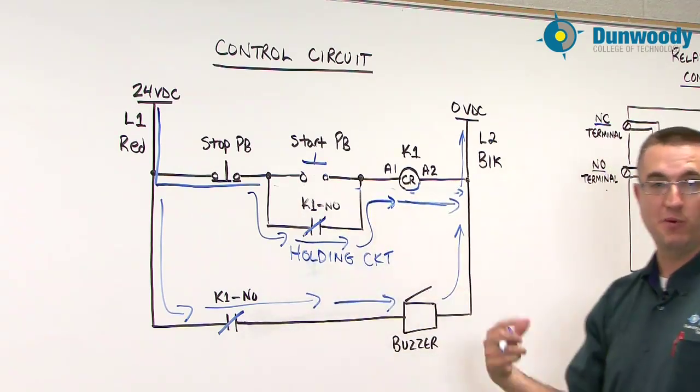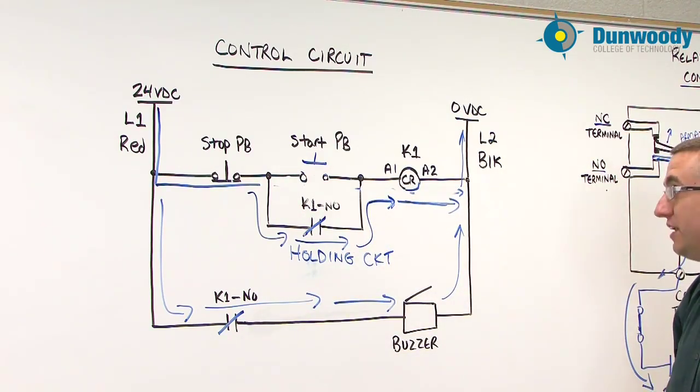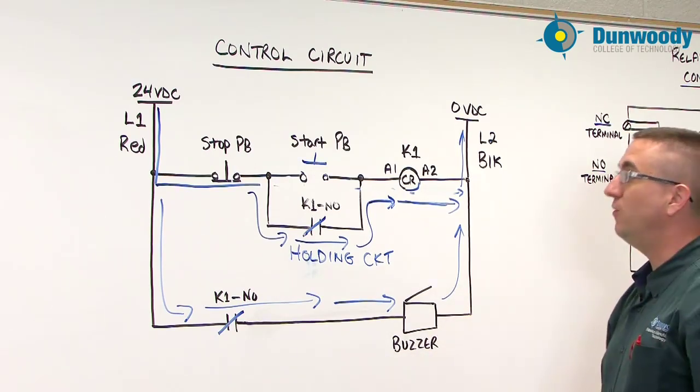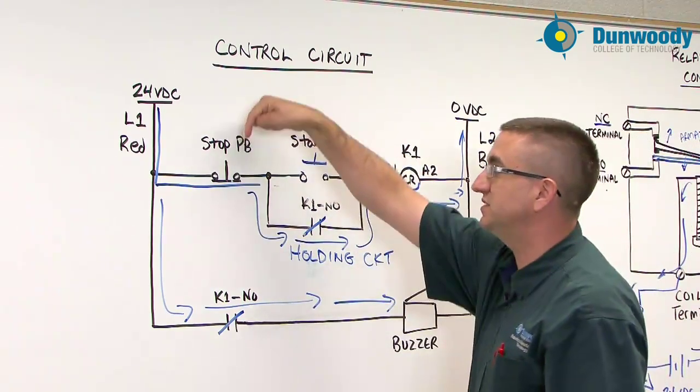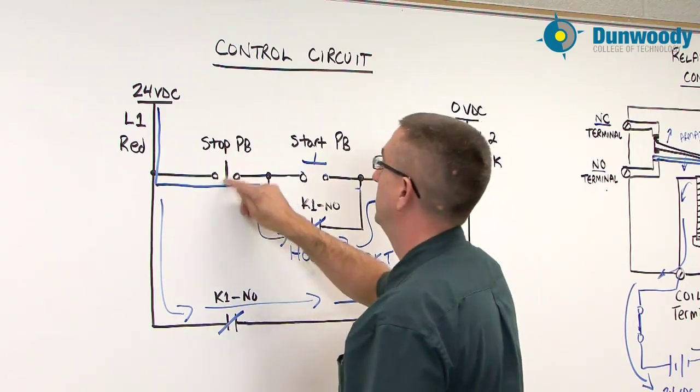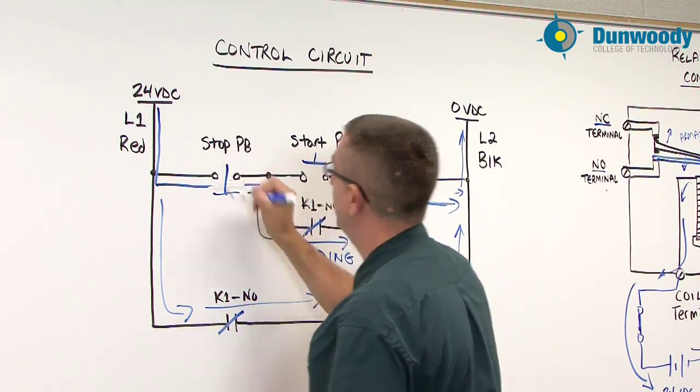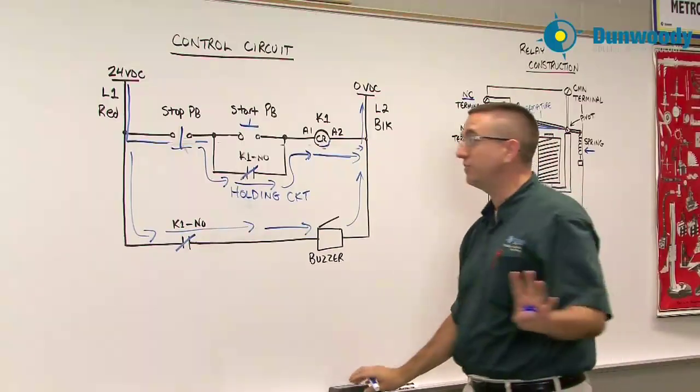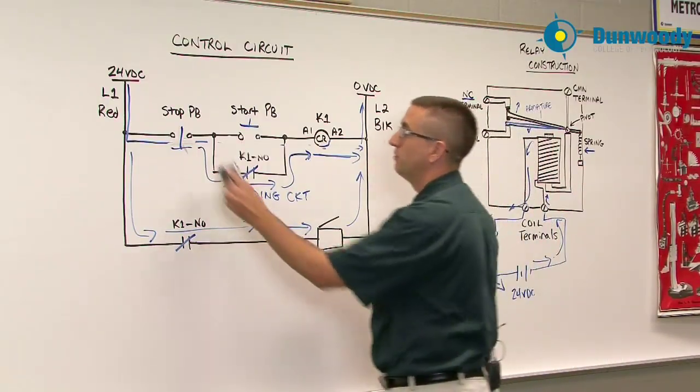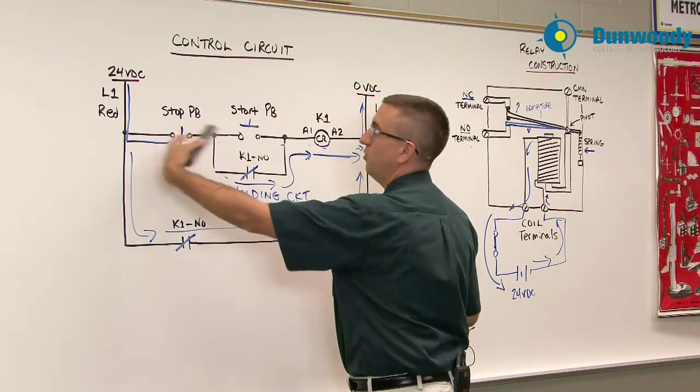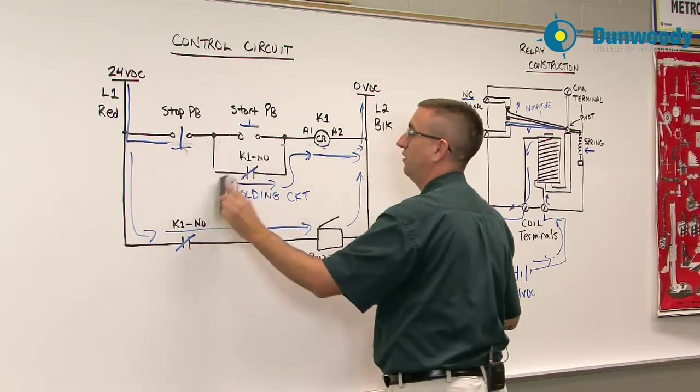So both of the contacts are going to remain closed. And now if I want to shut this circuit off, the only way to shut this circuit off is to press the stop push button, which is a normally closed push button. It'll look like this now. That's going to release all of the current. We're not going to have any current. We're going to remove current from our circuit. There's no way for electrons to flow through here.